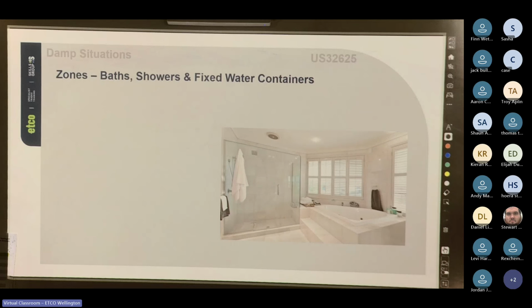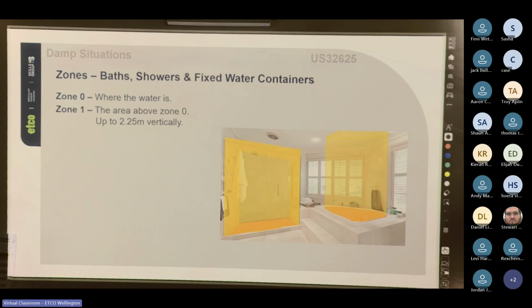So zone 0 is where the water is. So it's inside the bath, shower, spa, or pool, anywhere fully exposed to water. So zone 0 is the surface of and inside of the water. Cool. Zone 1, the area above zone 0, up to 2.25 meters vertically and directly surrounding a bath or shower. So basically from the water up to a height of 2.25 meters vertically.